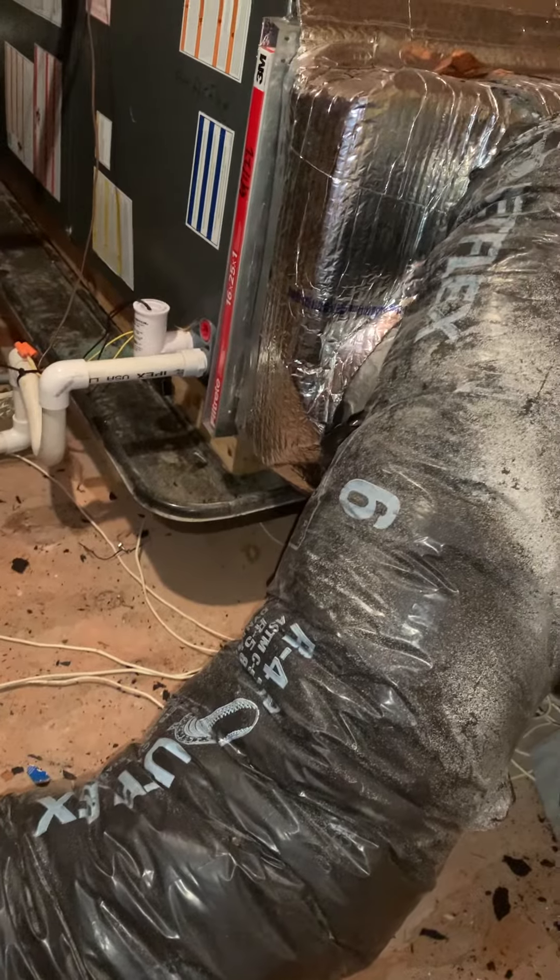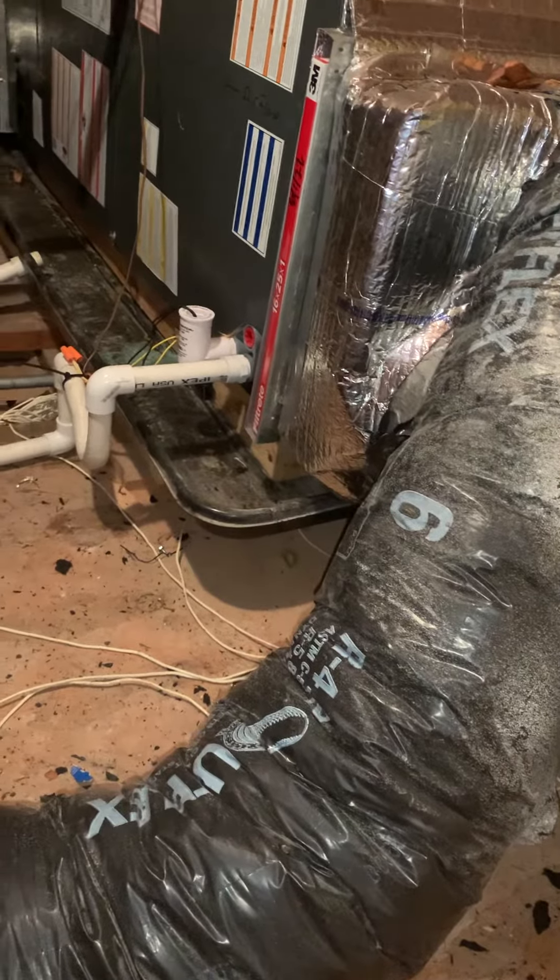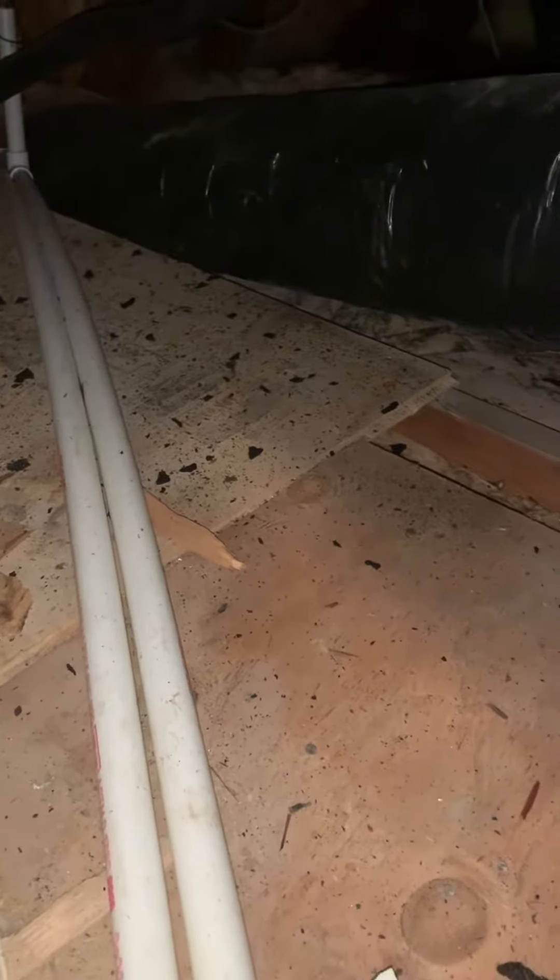Looking at getting a new safety pan and safety switch, and making sure the drain is insulated and brought over properly. That one is just poking up — I don't know why. Wire is running through that unless they were using it just to get the outdoor wiring out, but that's running through a drain.